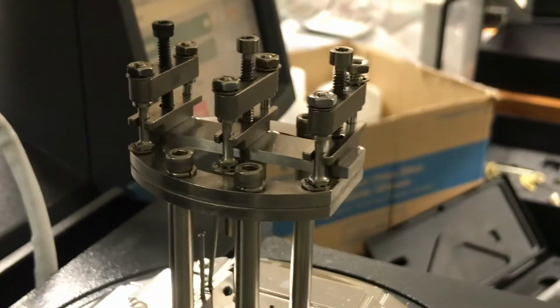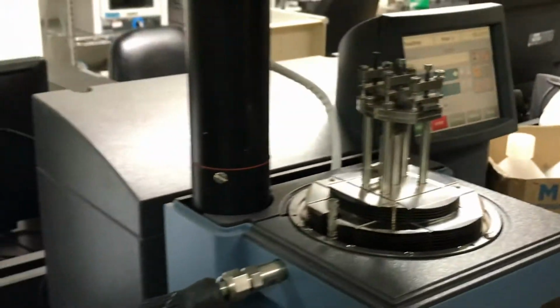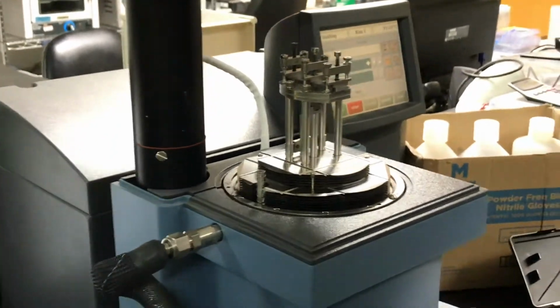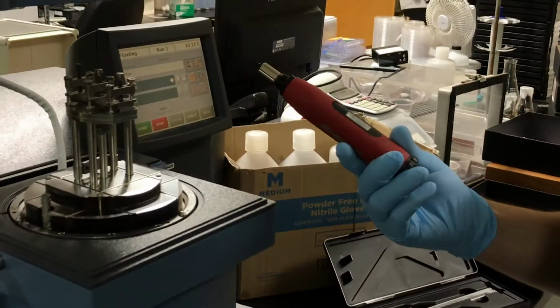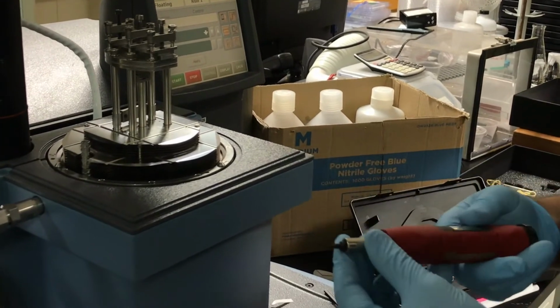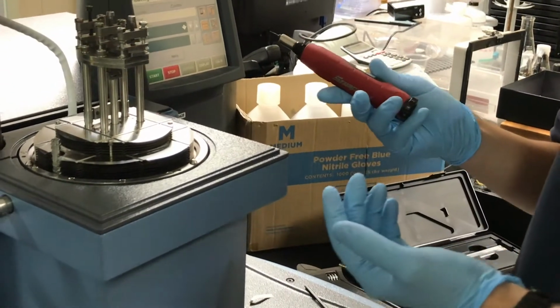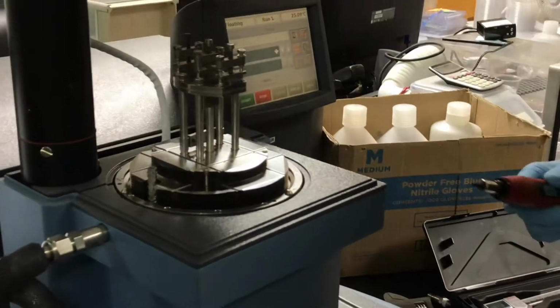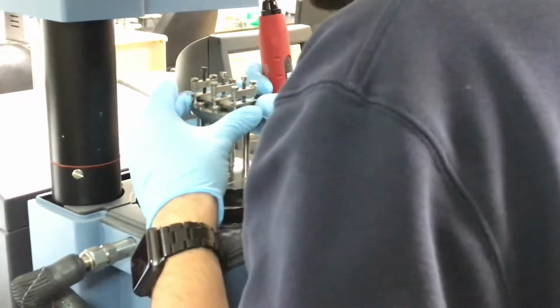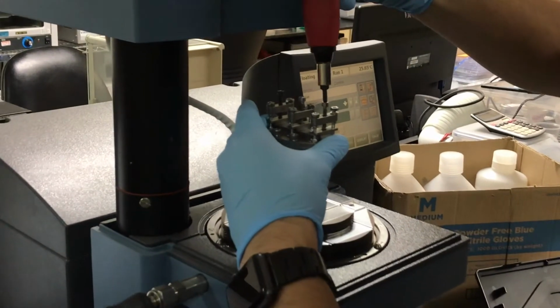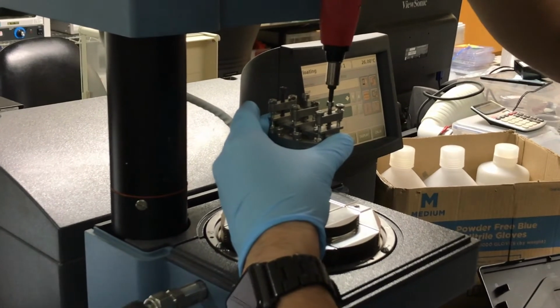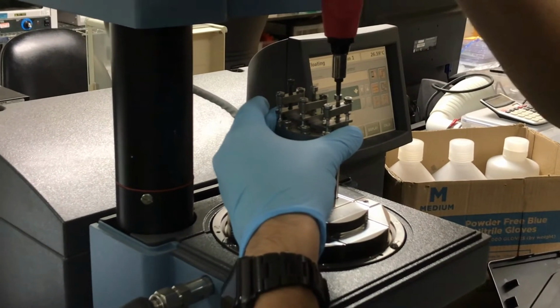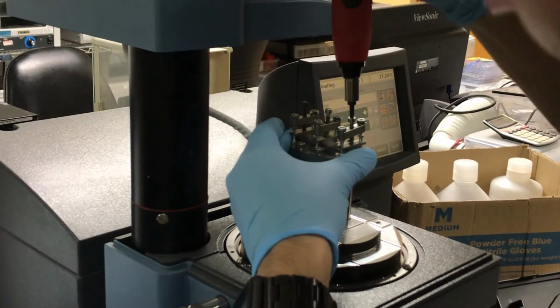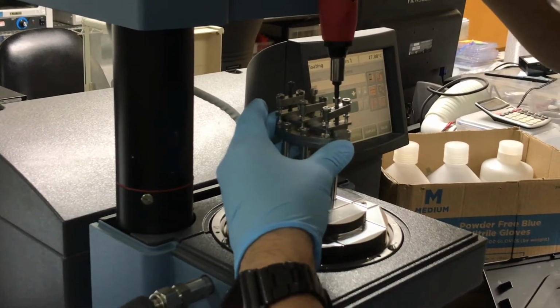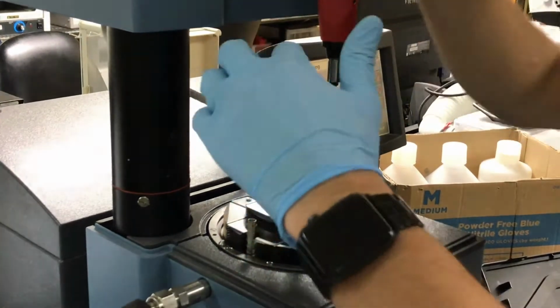And now that it's in position, you can go ahead and torque down the screws. So that's one thing that you'll need, a torque screwdriver. I think they recommend between 8 to 10 inch-pounds. So I just set it for 9, which is right in the middle. Now that this is in place, you can go ahead and torque down the screws. It's the 3 screws that you clamp down on each? Yeah, it's this one and that one.